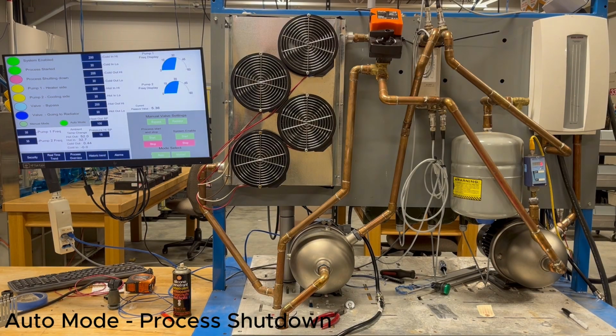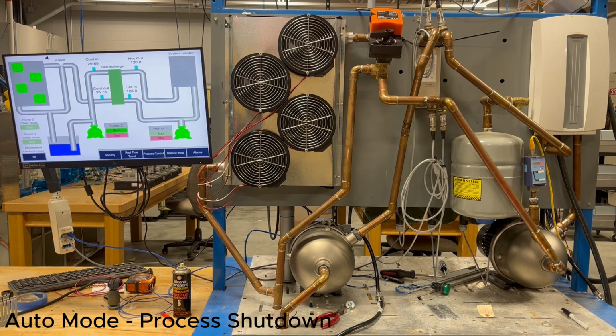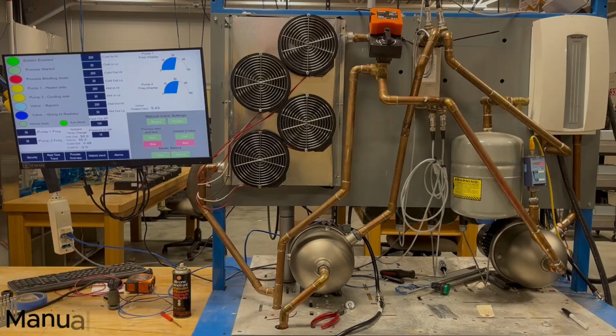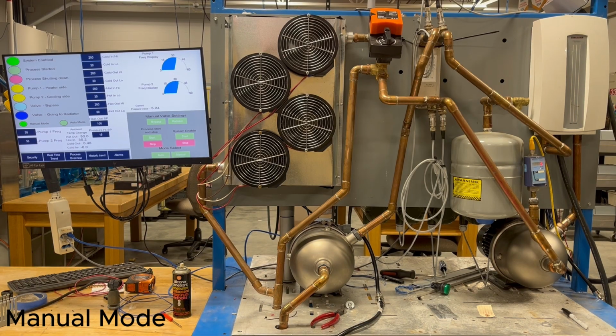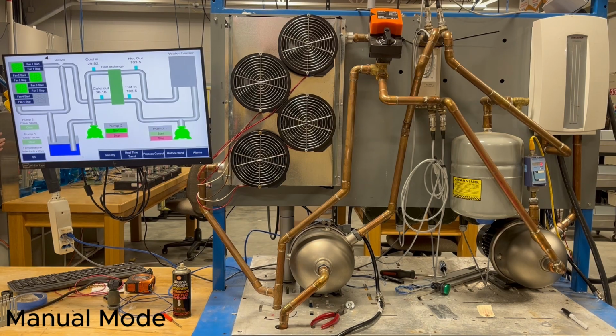In order to shut down the process, we will hit the stop process button, which will turn off the water heater but keep the pumps on while directing flow through the radiator and turn the fans on. The fans will follow the same staging process as before, and once the temperature is seen as safe to shut down, then both pumps will stop as well. And in manual mode, you are given the option to start and stop pumps and fans manually, as well as send flow through the bypass or radiator with a click of a button.